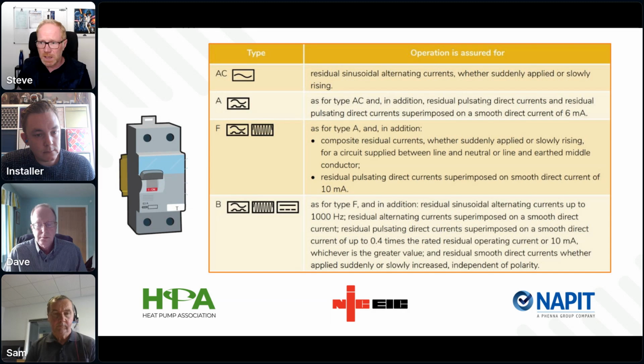Some type Fs that detect mixed frequency may also be suitable for certain kinds of heat pump inverters. Again, manufacturer's instructions. And that is why the characteristics we talked about in table 1 are so important. And another reason is that type Bs, if you just go for a blanket approach, are more susceptible to nuisance tripping. So although they're the daddy of the thing, due to their complex electronics and sensitivity to harmonics, maybe some interference, in some circumstances where DC leakage is not present, they could trip. So if you put a type B in, you could actually be causing yourself more of a problem.